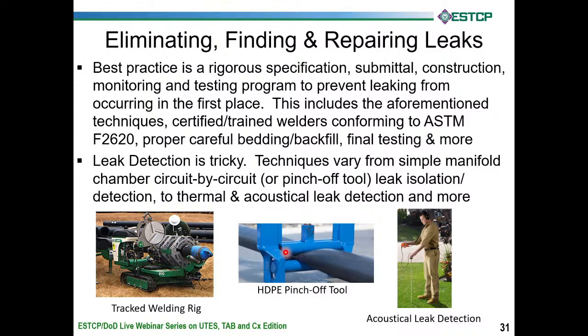We've never tried that, but at the two-star general project in Albany, we had one leak there, and we found it using the methodology of being able to pinch off the branch circuit, isolate it, and then get rid of the leak. But we were pretty happy that out of miles and miles of piping and 306 boreholes that we only found one leak after the system was made operational.